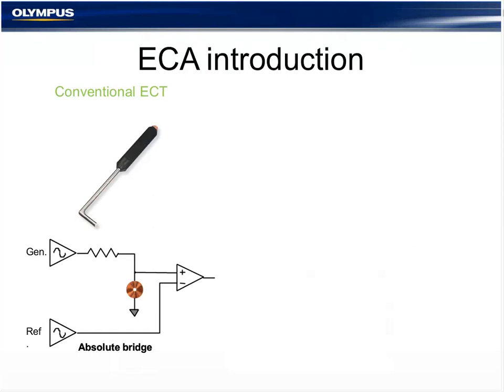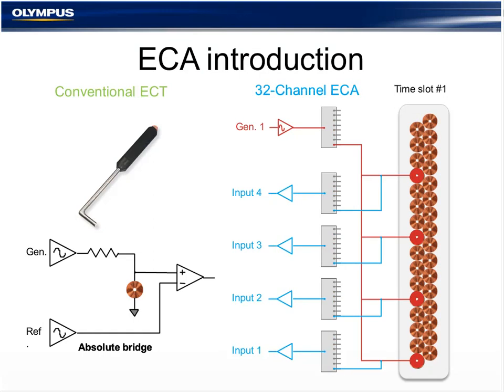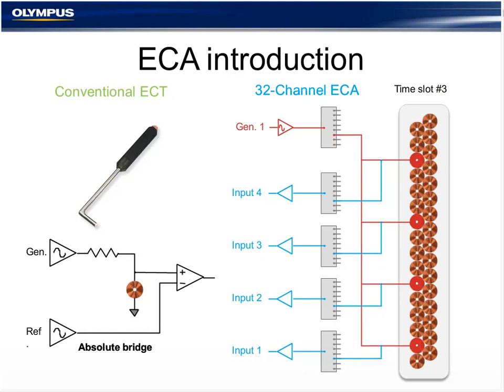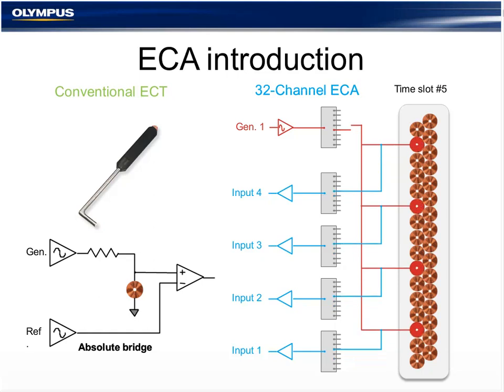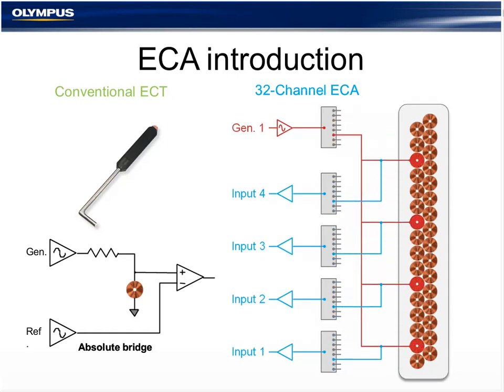Eddy current array: if I use one of the most known probes in the industry, a conventional absolute pencil probe, and basically apply that to an array, 32 times this same probe, we would have basically the same basic wiring, except that the different coils get activated at different times, very, very fast, by an electronic switcher called the multiplexer. All those switching intervals are called the time slots. So the time slots are the intervals where each of the coils gets read. That's as far as this explanation will get, because in this webinar we only need to know that it's an electronic scan, without going into more details.